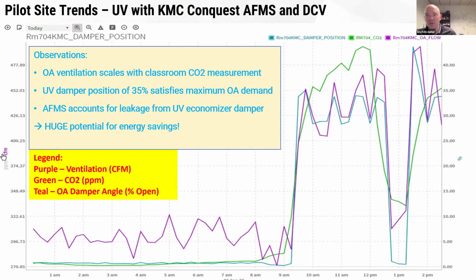When we applied our TrueFit AFMS to that unit ventilator, we actually found that they were meeting their ventilation minimums just in the leakage of the unit ventilators themselves. Again, temperatures don't care where that air comes from. So we're giving the building credit for any leakage through the damper, through the face, that sort of thing. Anything that affects that mixed air equation number, you get credit for. So in this case, we actually could close down the OA damper even further.